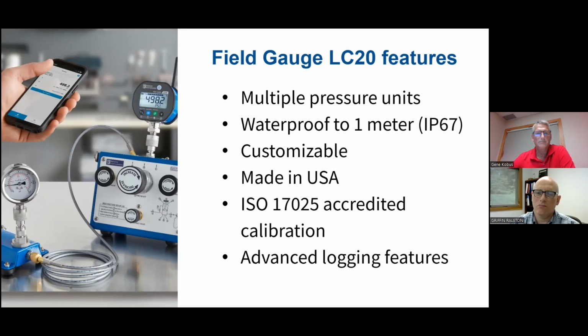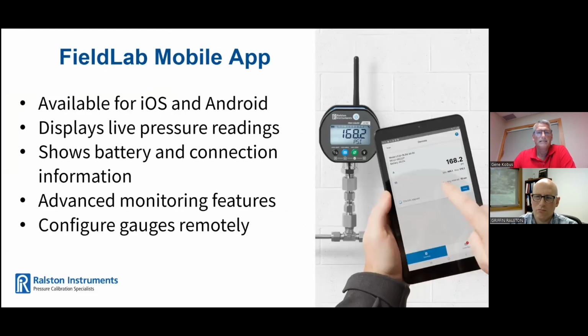The LC20 was designed and assembled and calibrated and supported in the USA. Our lab is ISO 17025 accredited, and all LC20 gauges come with an ISO 17025 accredited calibration and measurement uncertainty certificate. Logging is done directly on the LC20, so if it disconnects from the Field Lab mobile app, the data is preserved. You can also log multiple devices at once on the Field Lab mobile app. It's available on Apple and Android platforms. Displays live pressure readings of all connected devices, displays battery and connection information for connected devices. The mobile app will warn the user if the data set is full. If the data set fills up, the gauge will stop logging to preserve data. You can change the pressure units, update logging intervals, and start and stop logging remotely.